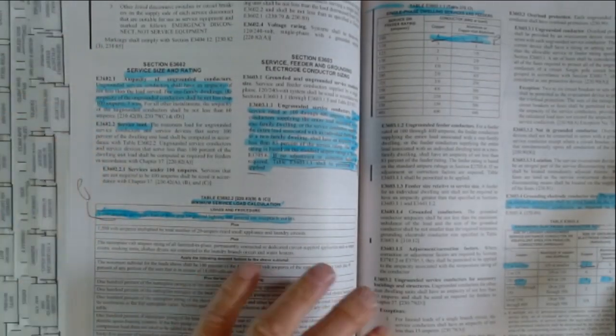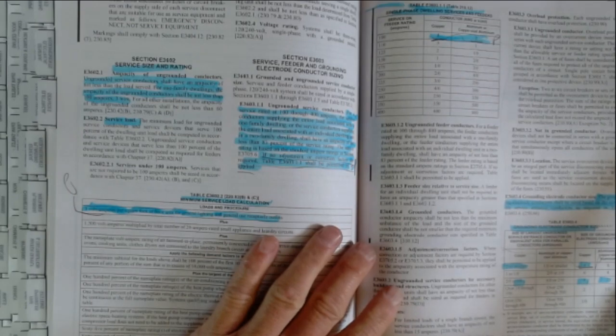Yeah, know your minimum's 100 amps for a house. 50 amps is a mobile home. Oh yeah, here's another one you need: 3 volt amps per square foot if you're sizing lighting and general receptacle uses. So 3 watts basically. Just keep that in mind.